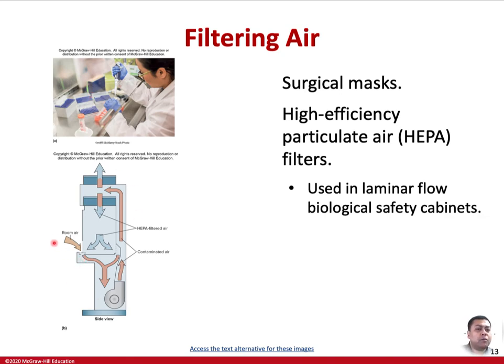In the schematic, what you can see is the environmental air is sucked in, and through a blower, it is circulated through a HEPA filter, and the HEPA filtered air is pushed into the chamber. And this creates a positive pressure in this air cabinet.